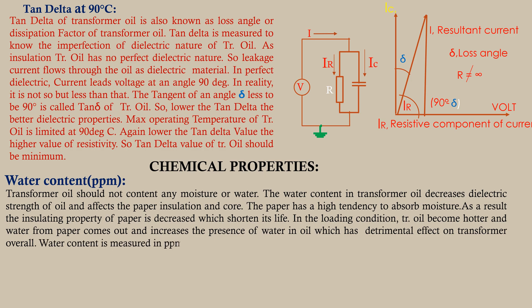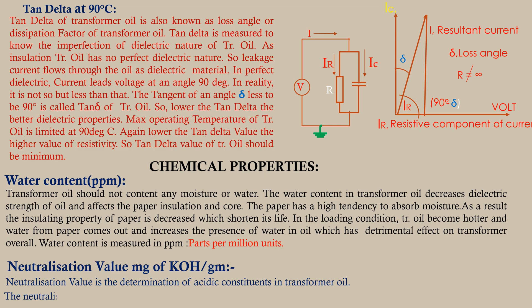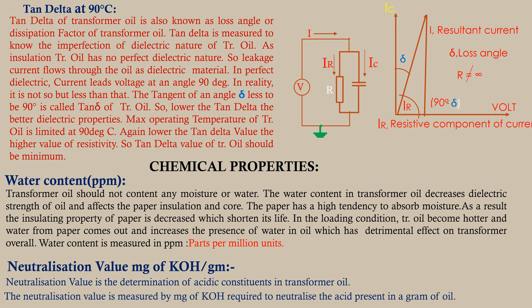Water content is measured in PPM (parts per million). Neutralization value is the determination of acidic constituents in transformer oil. It is measured by the milligrams of KOH required to neutralize the acid present in one gram of oil.